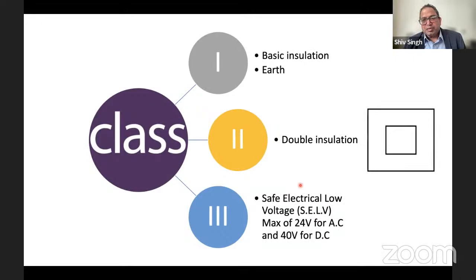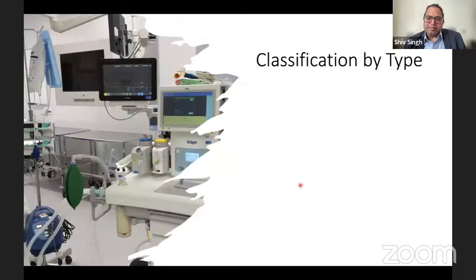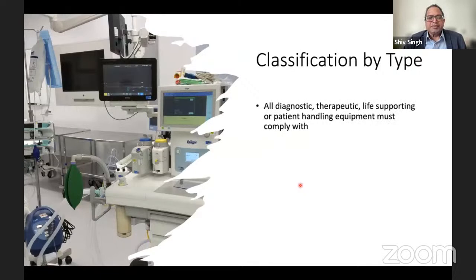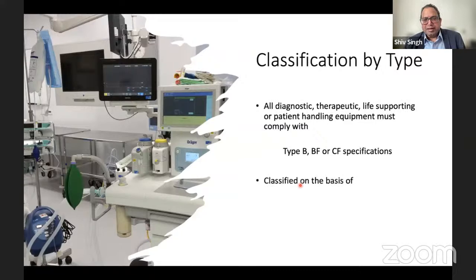Okay. The next classification is classification by type. Any diagnostic, therapeutic, or life-supporting equipment used in intensive care or in the theaters must comply with this classification. And this is type B, BF, or CF. This classification is based on something called allowable leakage current. So unless you understand what permissible leakage current is, you cannot define this equipment.